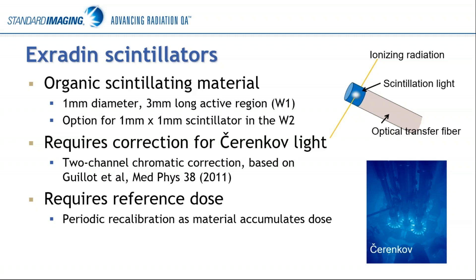This correction allows us to do a couple of characterization measurements, which I'll talk about next, and use the correction factor we get from those characterization measurements to remove that stem effect. These are not absolute dosimeters — you do have to give them a reference dose if you want output in terms of dose, and periodically recalibrate them as the plastic accumulates dose. Just like your PMMA phantoms, the optical transfer fiber will yellow a little bit with radiation and with age, and that changes how it transmits the spectrum.